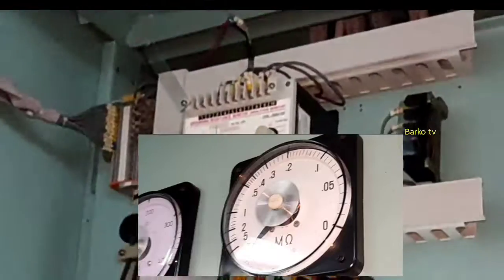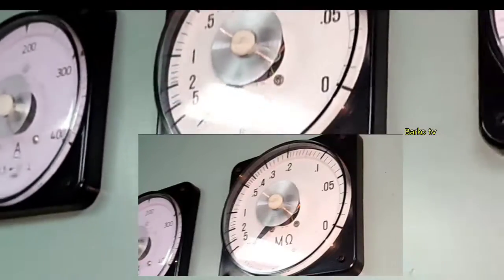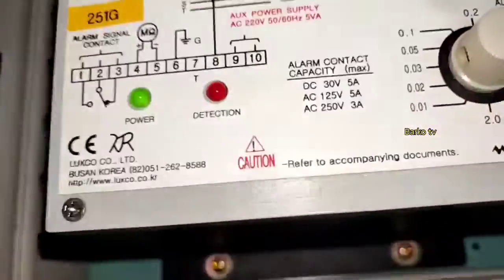Good day, I will share with you this very interesting topic for our 220V low insulation monitor. As you can see, it's reading almost infinity, and I wondered why the detection LED, when I press air test, it won't come up or trigger.